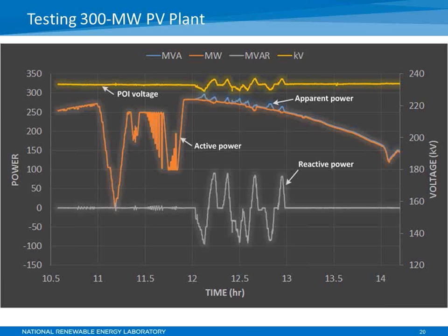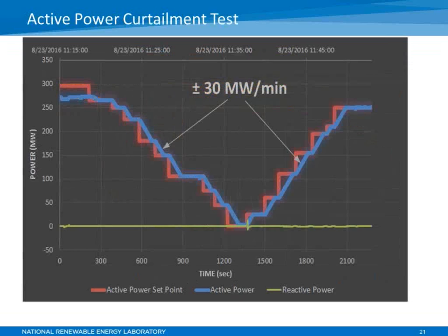There are many tests compressed in this time series, but the main takeaway is that a large PV plant can curtail very fast, down to pretty much zero generation in about 10 minutes, and come back as fast. It can respond very fast to different active power control signals. And in the second half of the day, you see that the only changing characteristic is reactive power. And when it is changing, it's of course impacting the voltage on the 230 kilovolt line. And again, there are a number of tests compressed in that second half of the day. Another takeaway is that when active power is swinging a lot, the reactive power is largely not impacted, and vice versa. When we do these large swings in reactive power, it is not impacting the active power. So it's one demonstration of independent control of active and reactive power by inverter-coupled generation.